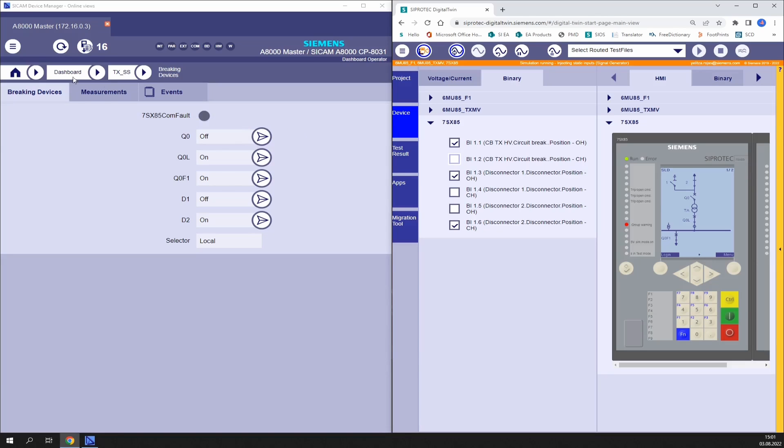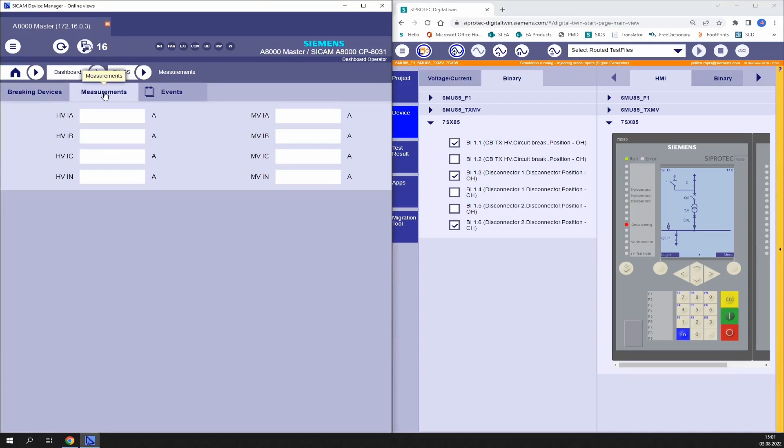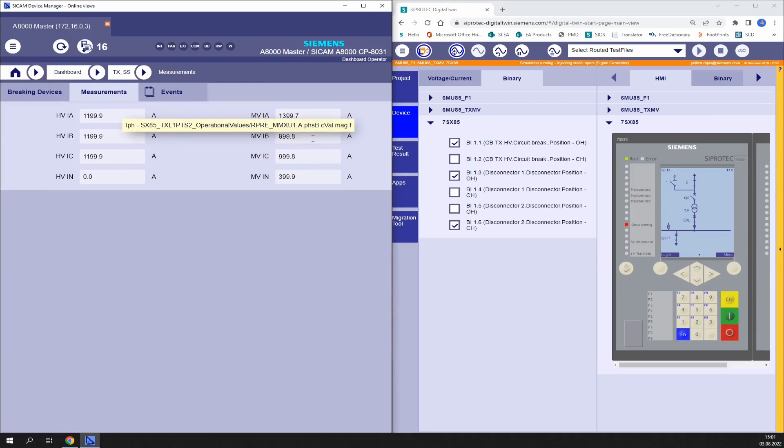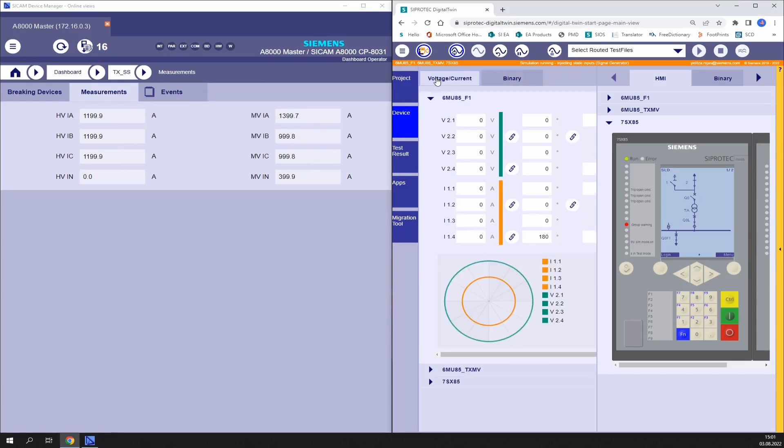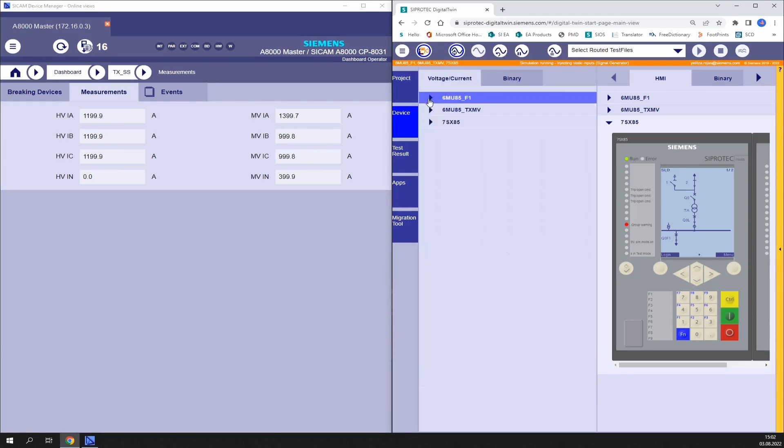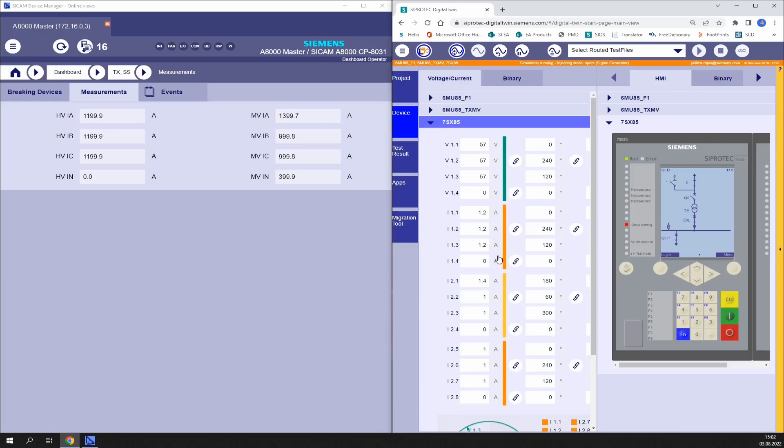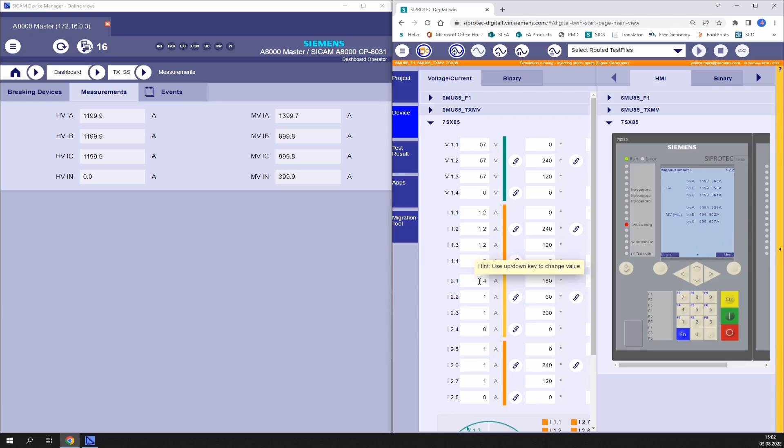We can also check measurements. Here we have the analog values corresponding to the high voltage side and the analog values of the medium voltage side of the transformer. Any change is automatically updated in the display of the 7SX85 and in the SICAM A8000.